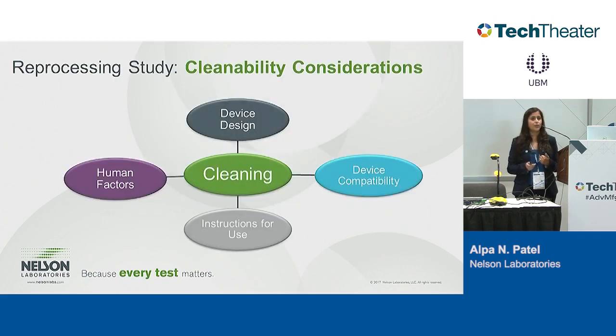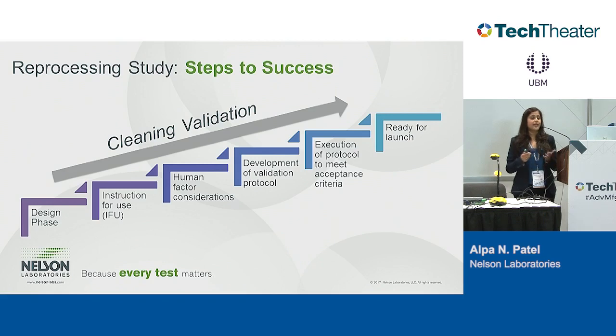When you think about cleaning in your areas, the first thing you want to think about is what affects this cleaning. Device design, human factors, instructions for use, device compatibility, all these things play a major role in performing a cleaning validation. Often what happens is we come at the end of the process where, you know what, I have a checkbox and I have to go through compatibilities first. Then I have to make sure that I've got packaging there and I've got bioburden tested, and cleaning and sterilization validations usually follow at the end of the process when you think about device validations or even the design phase of it.